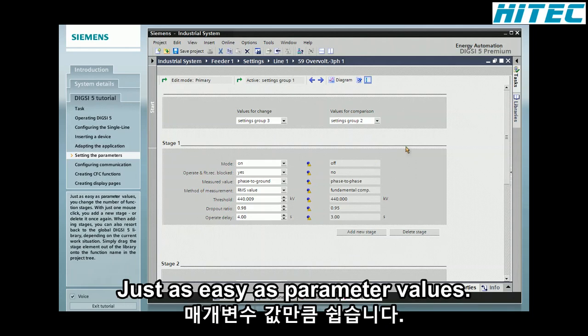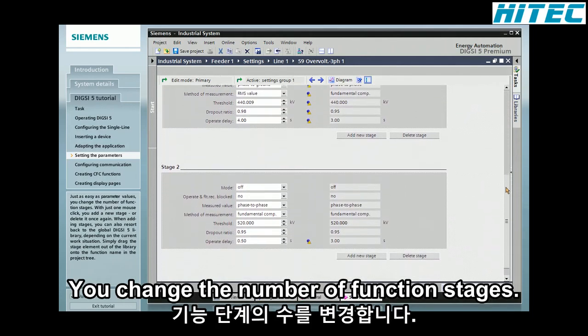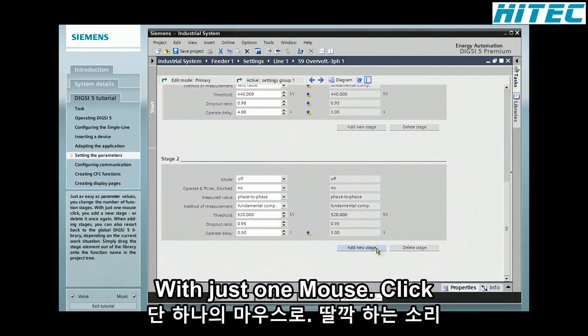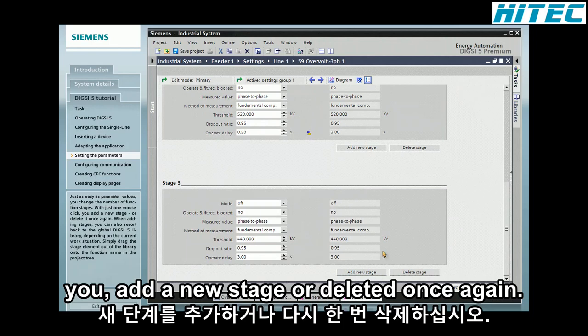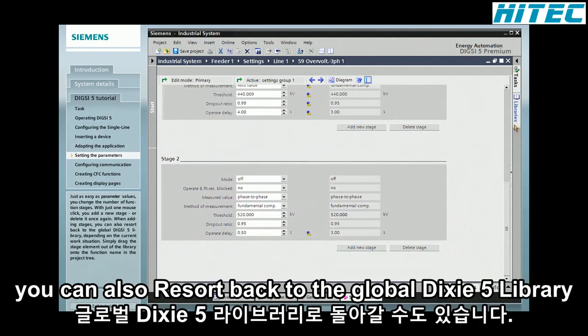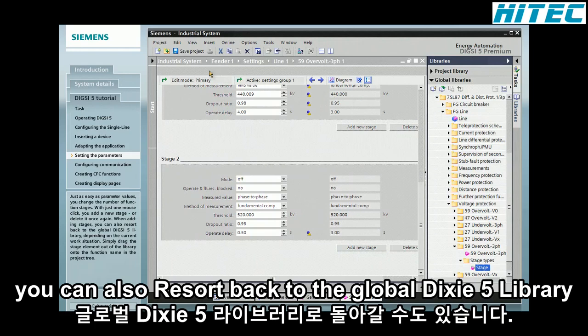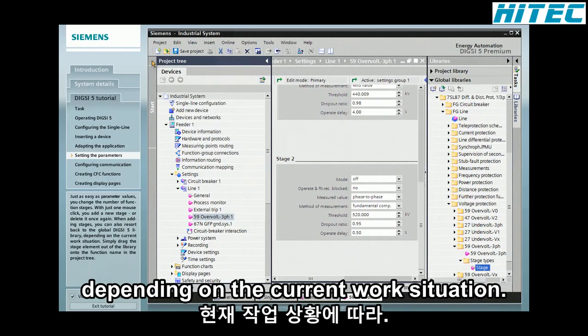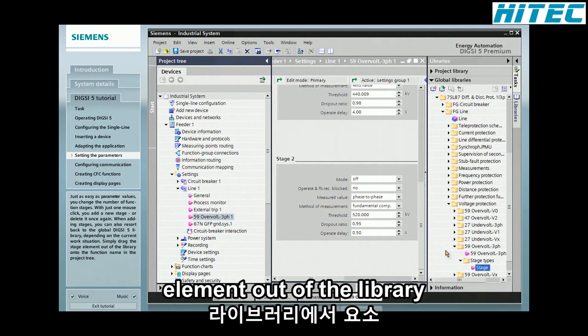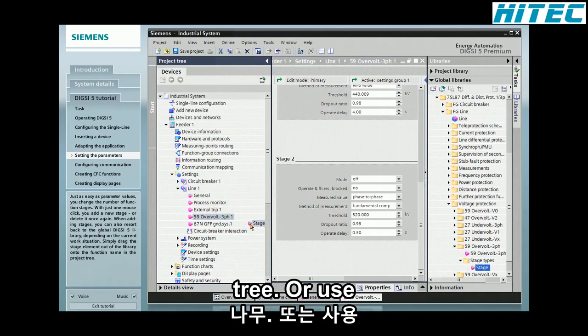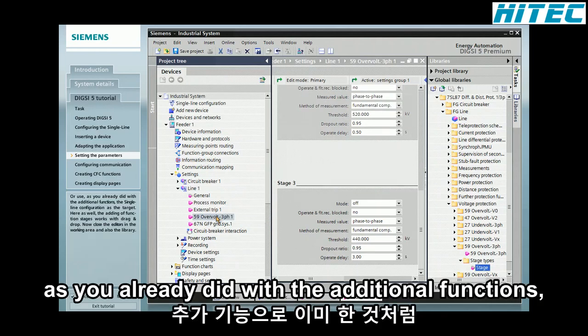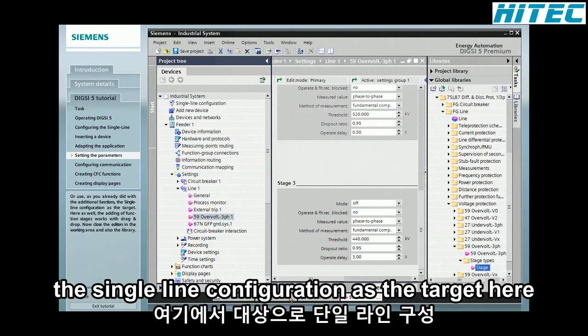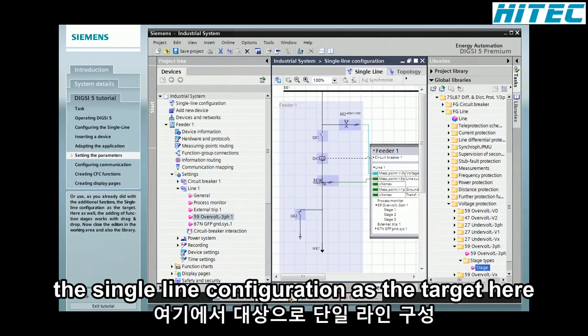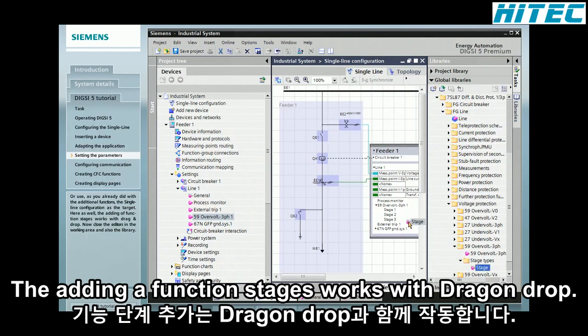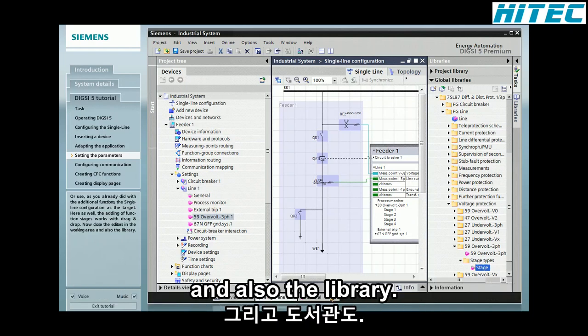Just as easy as parameter values, you change the number of function stages. With just one mouse click, you add a new stage or delete it once again. When adding stages, you can also resort back to the global DIGSI 5 library depending on the current work situation. Simply drag the stage element out of the library onto the function name in the project tree. Or use, as you already did with the additional functions, the single-line configuration as the target. Here as well, the adding of function stages works with drag and drop. Now close the editors in the working area and also the library.